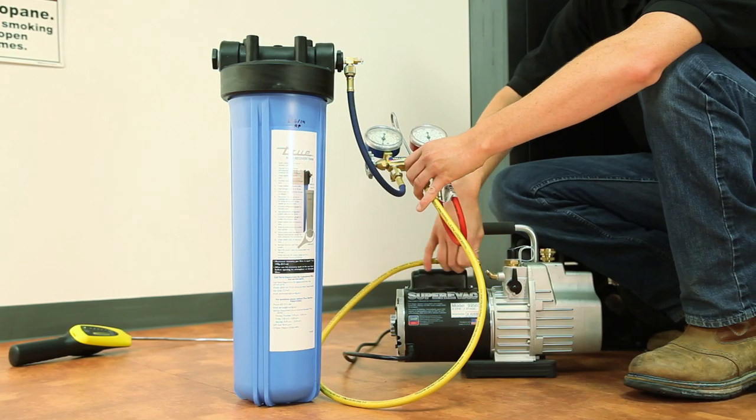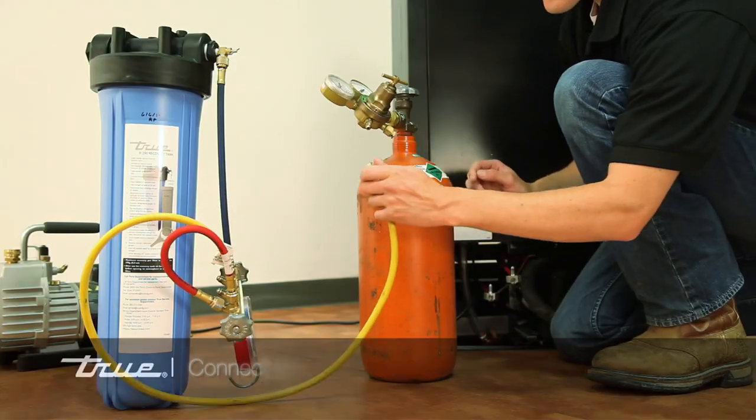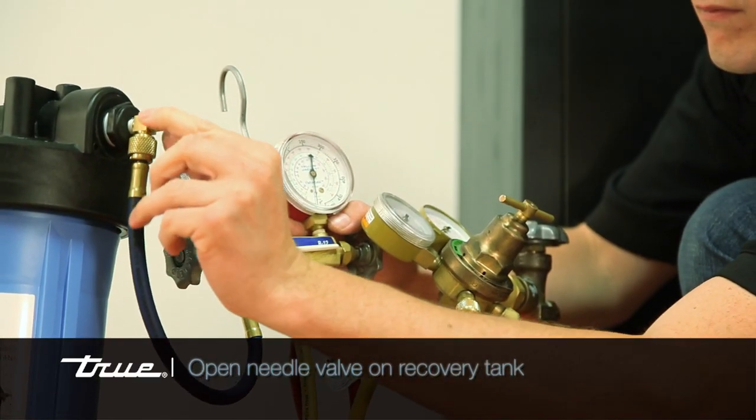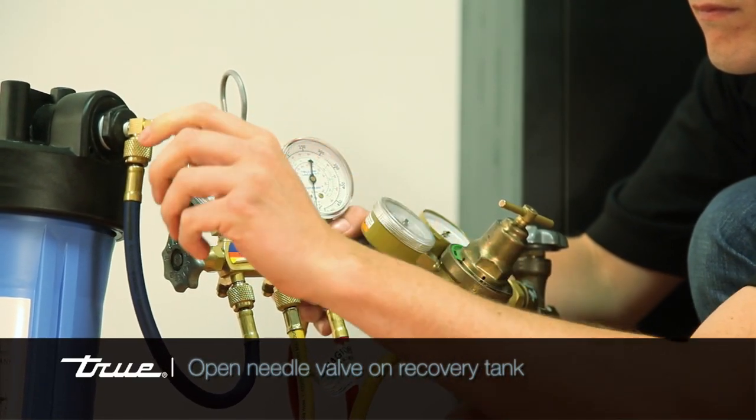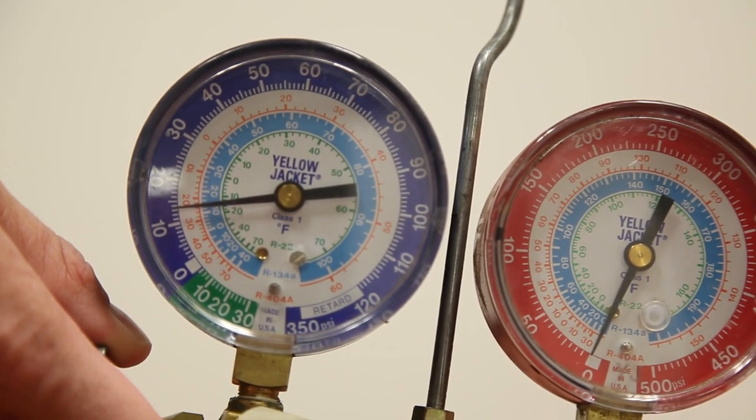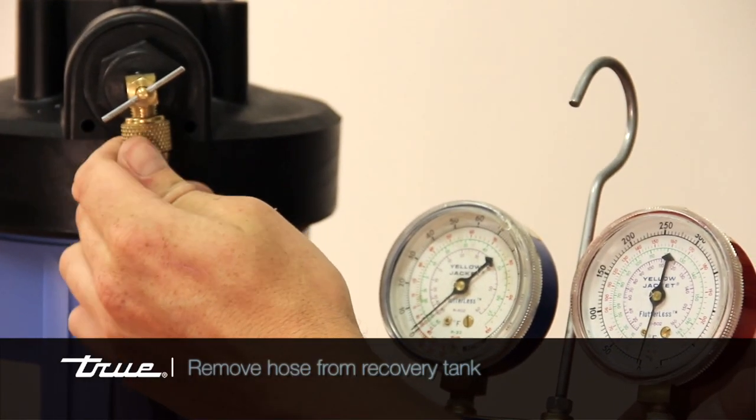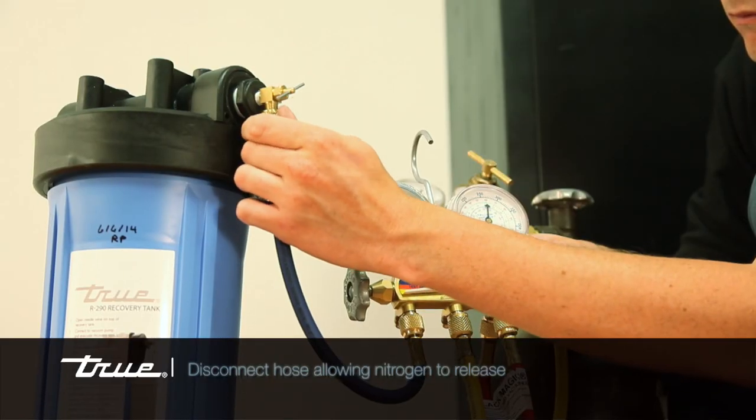Disconnect your gauges from the vacuum pump and connect to your nitrogen tank. Open the needle valve on the recovery tank, then break the vacuum by adding 13 pounds of nitrogen into the tank. The next step is to remove your hose from the tank and release the nitrogen.